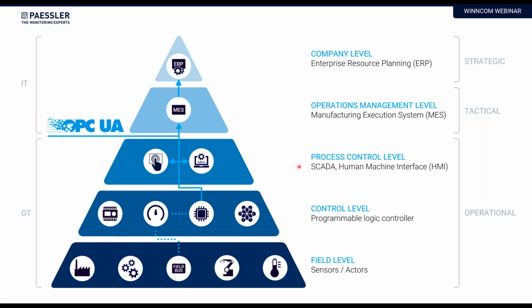At the process control level you usually have your SCADA system, your human machine interface. We don't want to replace SCADA, to be honest, but there's one buzzword worth mentioning: what happens when your SCADA system is down? We call it watching the watcher — how can you make sure your SCADA system is up and running? You may want to consider a secondary alarming path beneath your SCADA, and this is again where PRTG comes in.